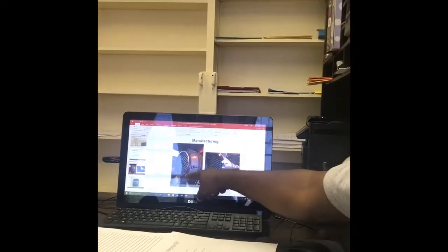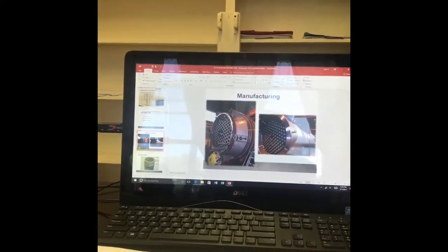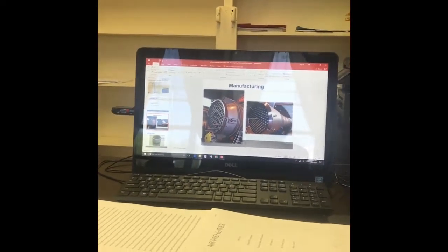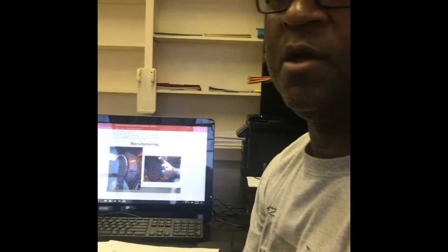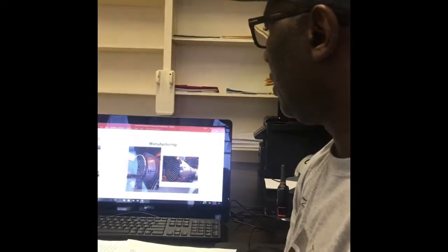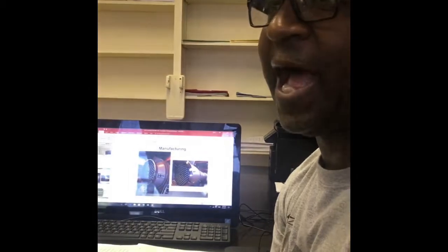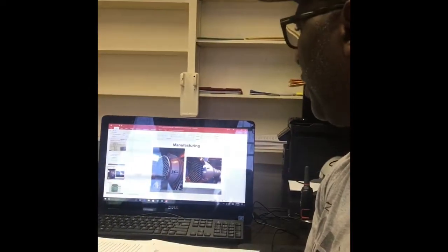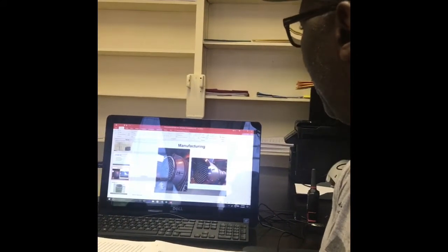But if you can see in this slide here, you see some of the piping sticking out. Basically what has happened is that those pipes and those tubes have become plugged. And just like our arteries in our heart, if they become plugged, now they have to work extra hard. And when they start working extra hard, they start expanding further than they're normally supposed to. Then the carbon black buildup from our furnace, where we inject air and gas and oil, goes up through these tubes, and the air is circulating around in those tubes, and the hot air begins to expand.